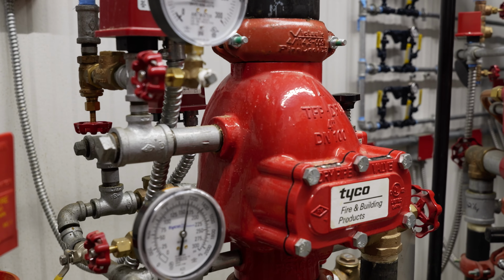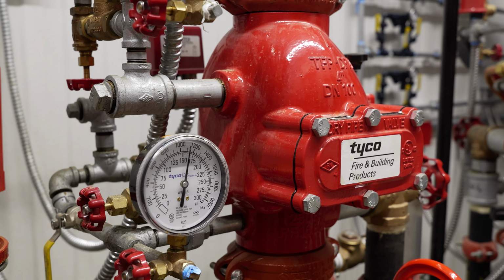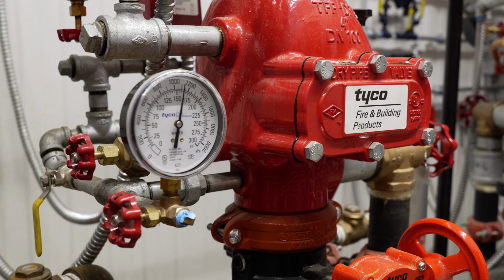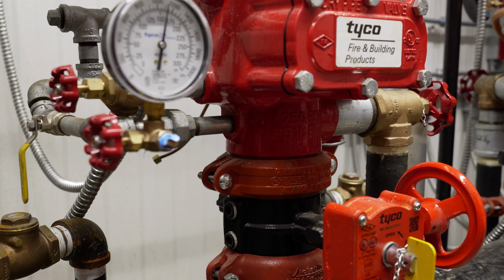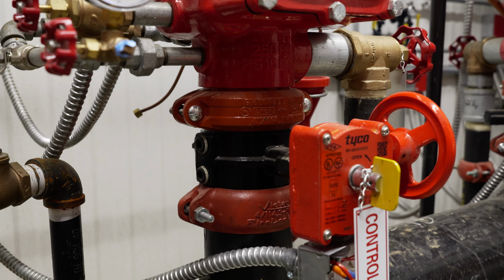Dry pipe sprinkler systems. There are two dry pipe systems in the building that protect the loading dock and mezzanine areas. These areas are intended to be maintained as coolers and above freezing temperatures. These are the simplest form of dry pipe system and are used in cooler spaces as they are more cost effective than the types used in the freezers. They are able to be full flood trip tested for annual inspections. Here's a short animation demonstrating the operation of these valves.